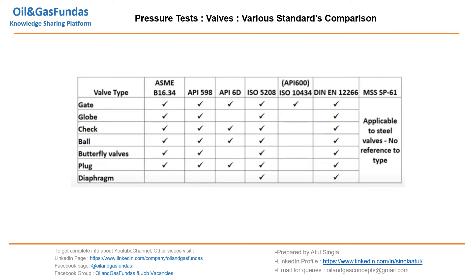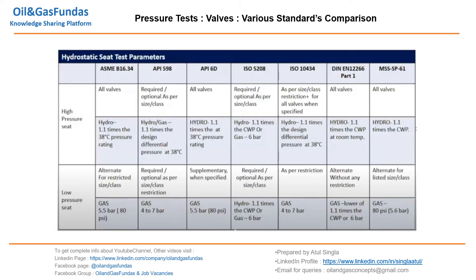Now we are going to compare the low and high pressure seat test requirements given in other standards. In ASME B16.34, the high pressure seal test is required for all valves under specified pressure and temperature conditions. As per API 598, it is required and optional depending on size and class, as discussed in detail previously. As per API 6D, it is required for all valves. As per ISO 5208, it is required or optional depending on size and class.